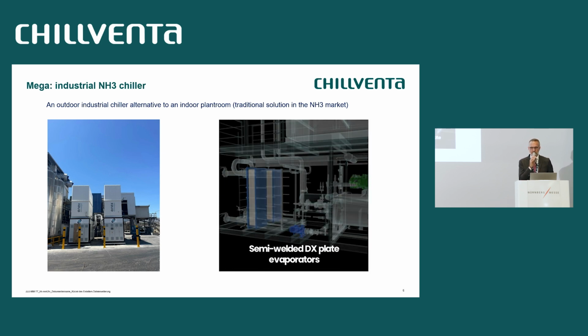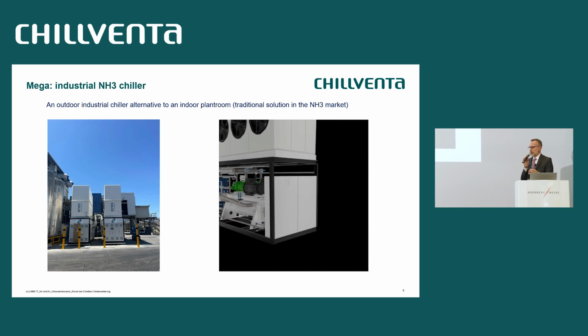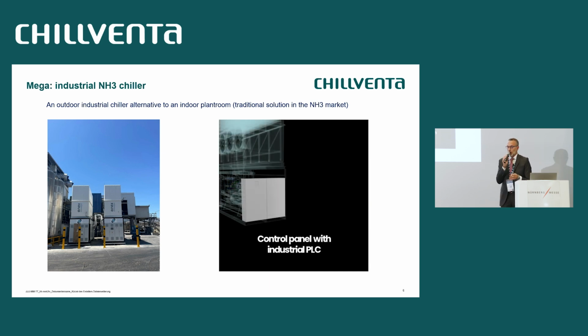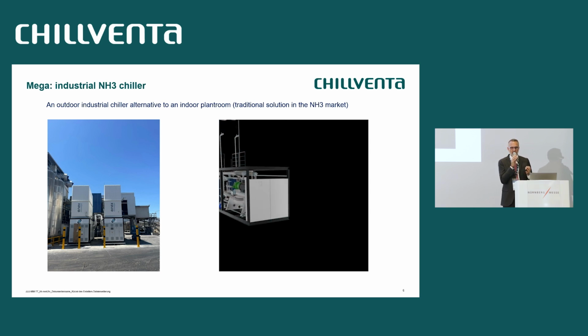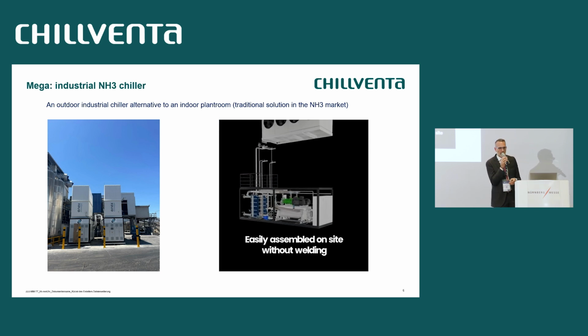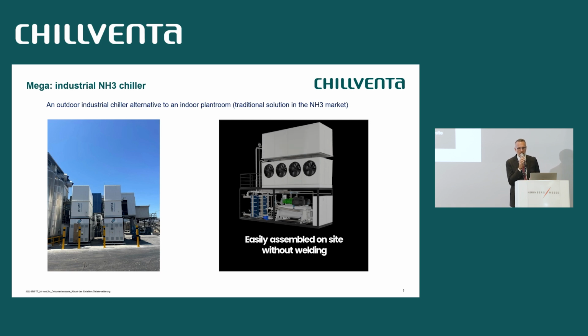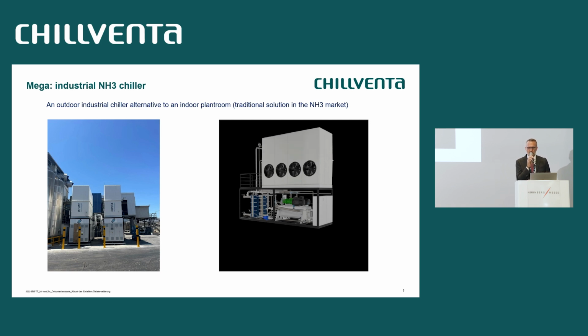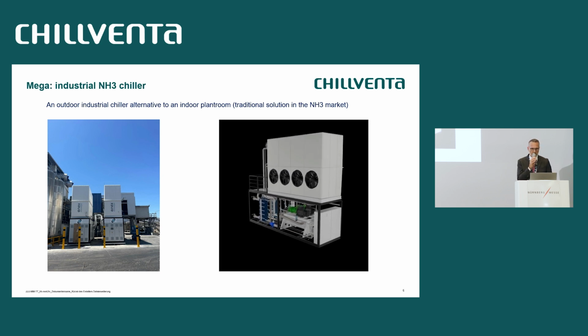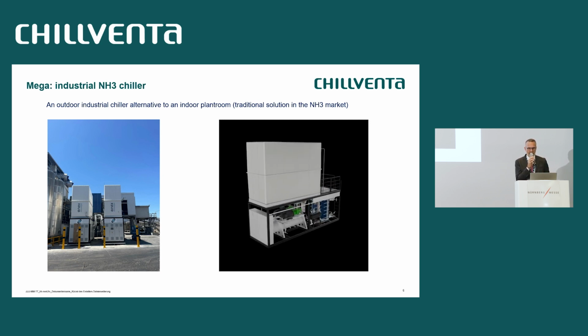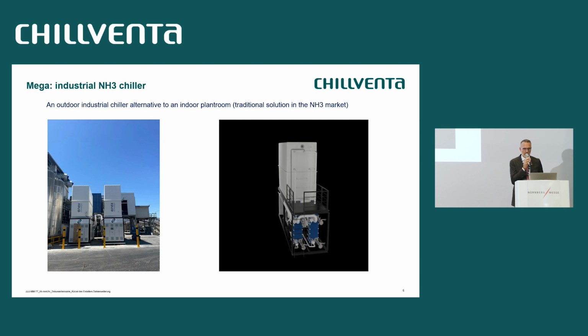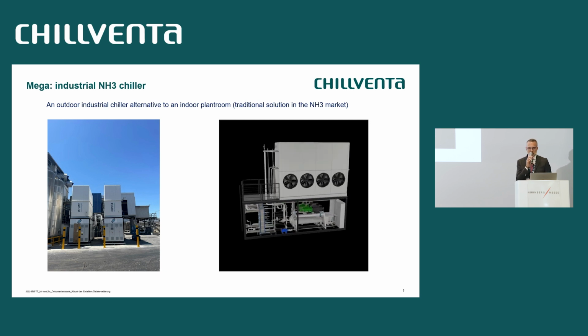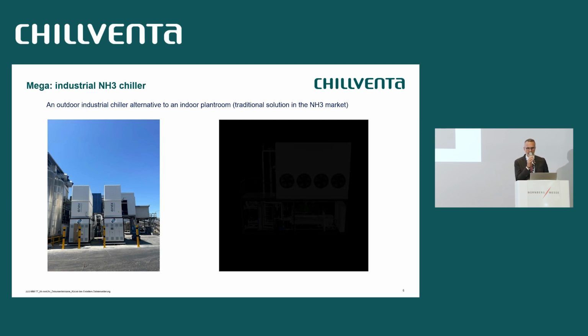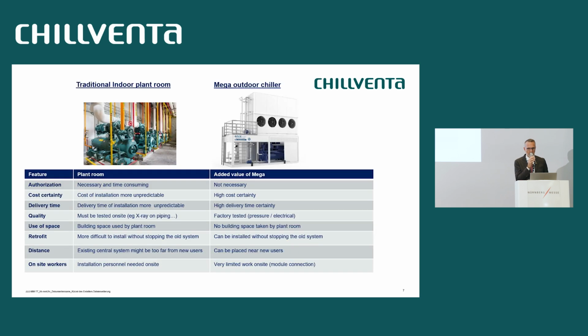We also have the possibility to install direct expansion evaporators, which help to reduce the charge. In this kind of unit, it is typical to have around 350 grams per kilowatt, so a very low refrigerant charge compared to traditional systems. And in the picture on the left, you can see an example of a real installation in a big industrial facility for an air conditioning application.